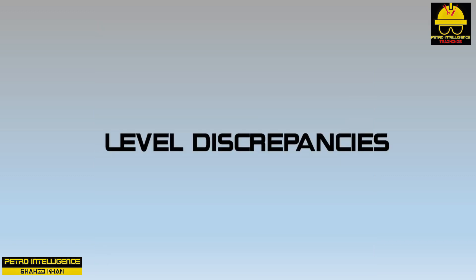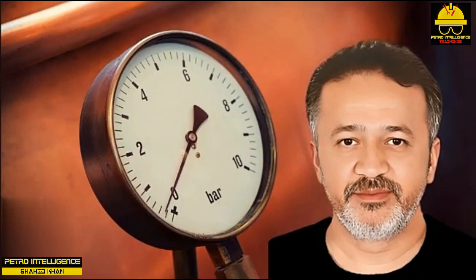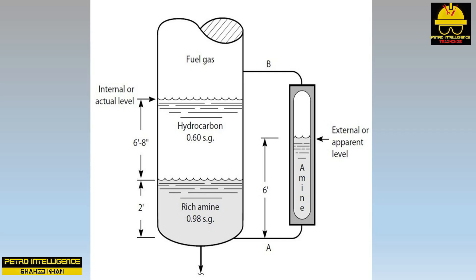Let's assume the gauge glass holds six feet of amine. Since the bottom tap is in the amine phase and the top tap is in the gas phase, liquid hydrocarbon is excluded from the gauge glass. To balance the weight of six feet of amine, the tower would need about two feet of amine and six feet eight inches of liquid hydrocarbon — meaning the tower liquid level would be about eight feet eight inches, or two feet eight inches higher than the gauge glass level.